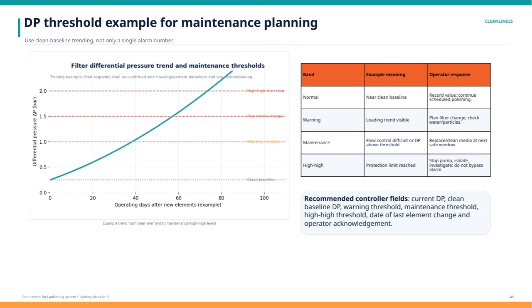Finally, if the high band is triggered, it means the protection limit is reached. The pump must be stopped immediately, the system isolated, and a thorough investigation conducted. Under no circumstances should you bypass this alarm. To effectively manage these thresholds, the recommended controller fields should include the current DP, clean baseline DP, warning, maintenance, and high thresholds, as well as the date of the last element change and operator acknowledgement. This structured approach ensures timely maintenance and prevents system failures due to clogged filters.